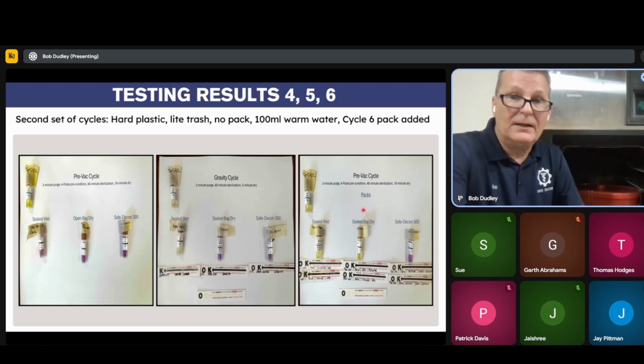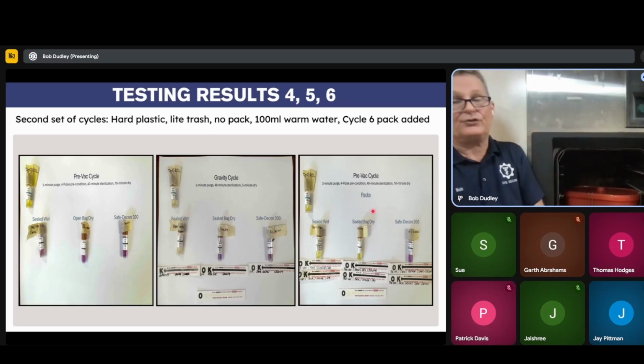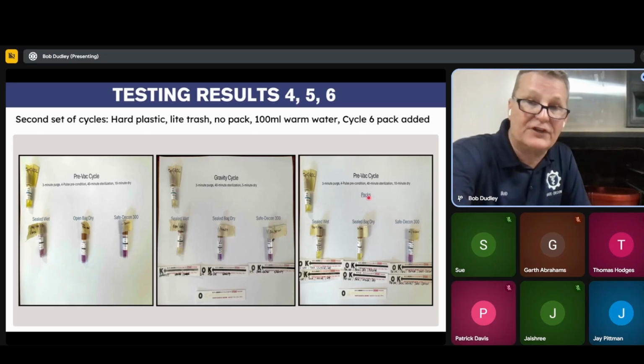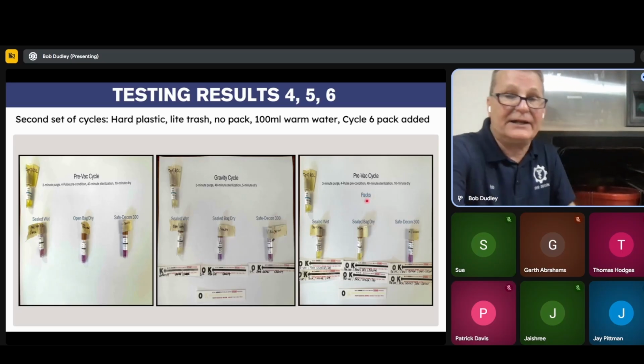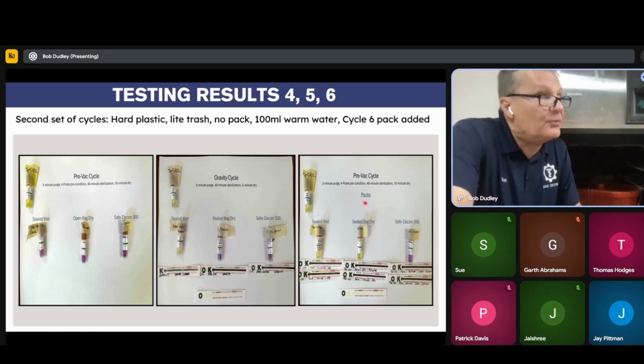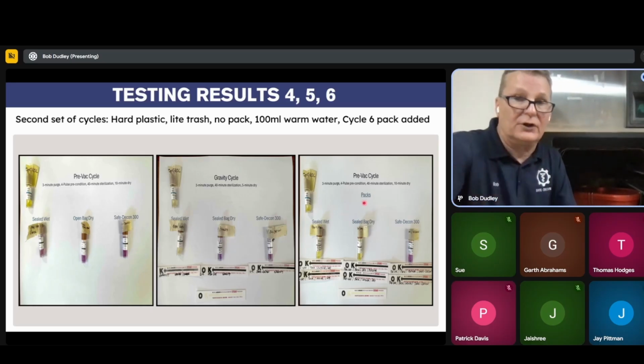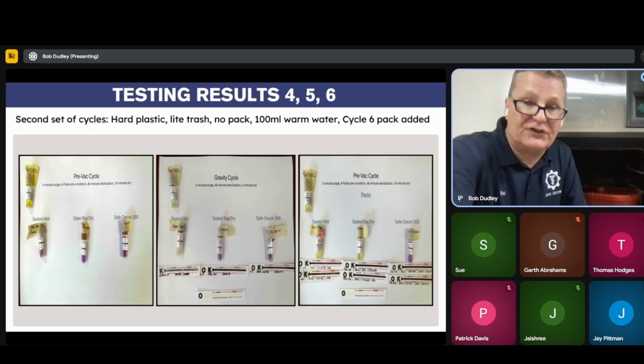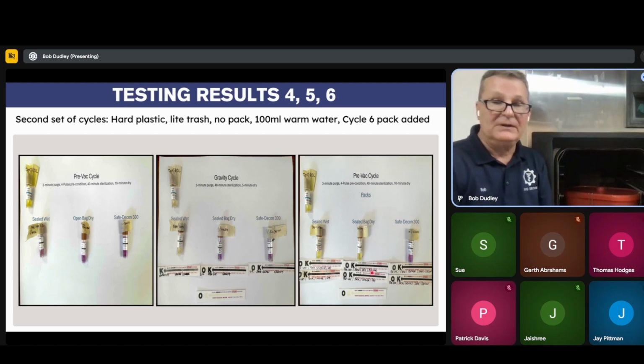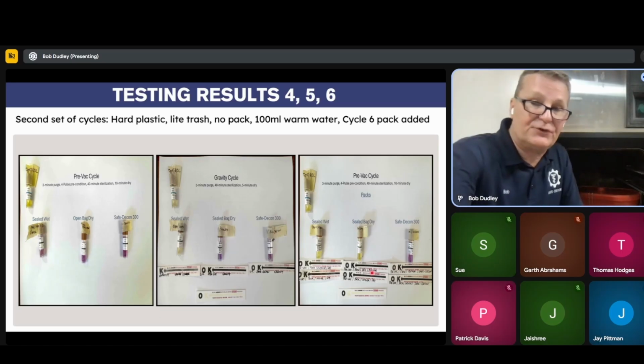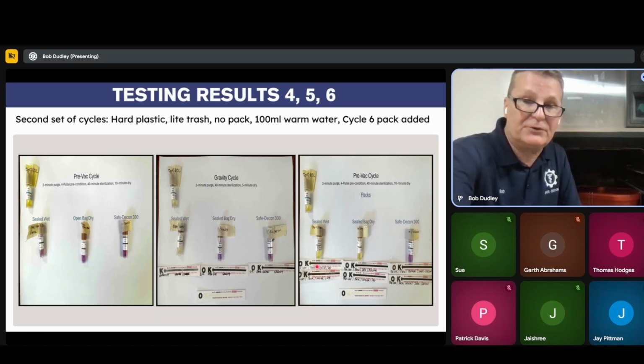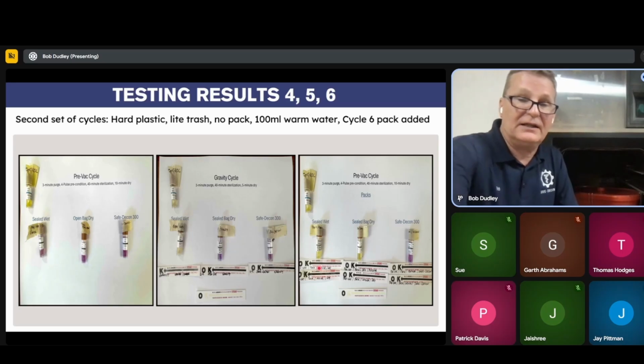It just closed. On cycle 6, I added the trash. And this is where you can see I added the packs. This one was just plastic on it. This was a sealed pack right here. Now, on the sealed pack, this is where I actually taped it down. I just didn't fold it over and let it go. You can see here that this bag burst and this one burst. And look here at your chemical strips saying, hey, Bob, we're good, man. We reached temperature. We had steam penetration. We had good temperature. And again, these are the poppers that indicate steam and 250 degrees.